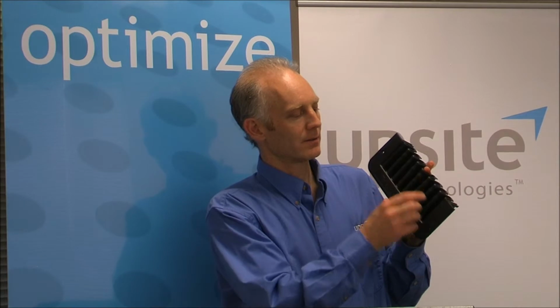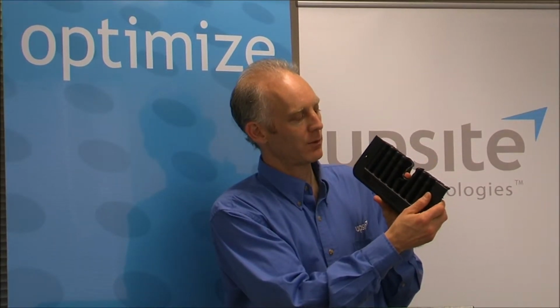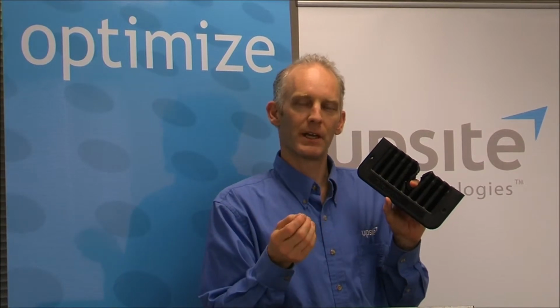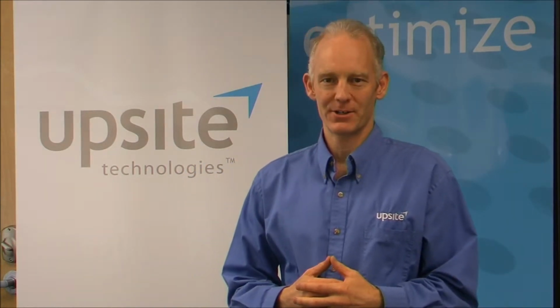The way that the elastomer wraps around cable penetrations creates a very effective seal, as will be demonstrated in the sealing effectiveness test data I'll show you soon. The ultimate performance metric of a raised floor grommet is its ability to sustain differential air pressure with minimal leakage. At Upsite, we test all of our products to benchmark leakage performance and use extensive leakage testing in the development of all of our products.